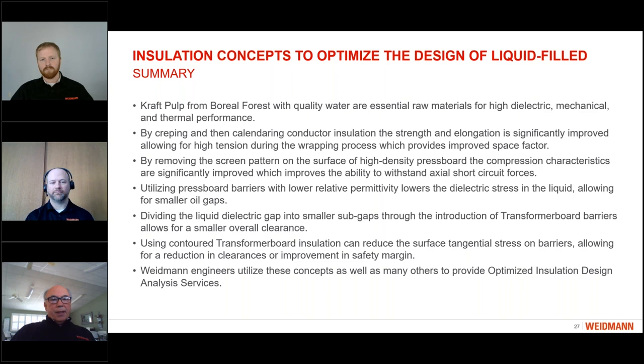Okay, so the next is this concept of the barriers themselves. Jason referred to the Weidmann reference curves. The concept of that is that the smaller the liquid gap, the oil gap, the higher the strength is. So if you can take any liquid gap and break it into smaller subgaps through the introduction of barriers, then you can get a smaller overall clearance. And if I take that concept and add it to what Brad presented about the lower relative permittivity, if I use lower density board for those barriers, as I mentioned before, then I can get even more of an improvement.